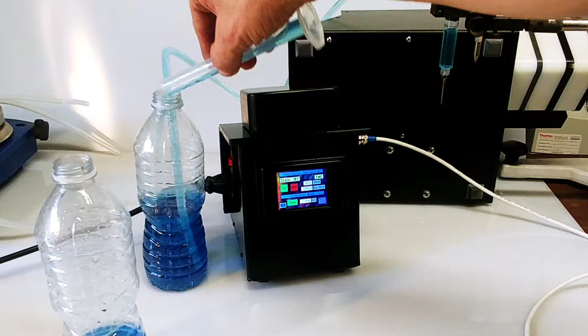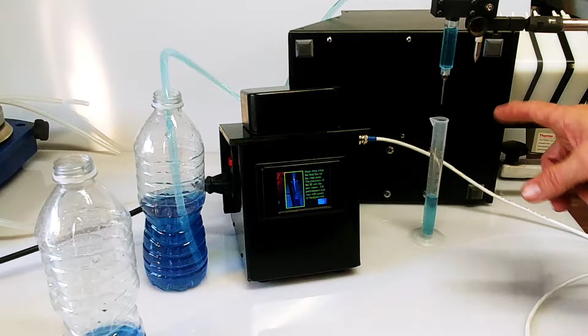One of the better features is that there's a lot of built-in help screens. So in setup, for instance, it tells you how the help screen runs, and it breaks down how you utilize the screens and what the various buttons do. When you go into a calibration mode, again, it tells you how to set the calibration up, how to set up the equipment with the graduated cylinder, and then what to set the fill to in order to be able to establish a calibration. The calibration relates the system parameters so that your RPM speed now relates to the volume that you're pumping. It's all in all pretty cool little setup.